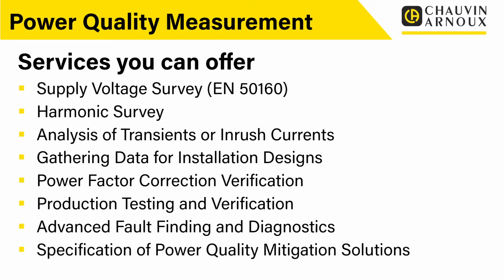And it can be as simple as, we're talking about type B, C, and D breakers. Just for your normal circuit breakers and RCBOs. Should it be a type B, a C, or a D? Again, if we do an inrush current assessment, we can have a look at that and we can specify the right characteristics of protective device. So it's a useful service there, and if you're working in these environments, having the ability to do that and to look on a graph and physically see the levels of inrush currents and how all that works, is really important.